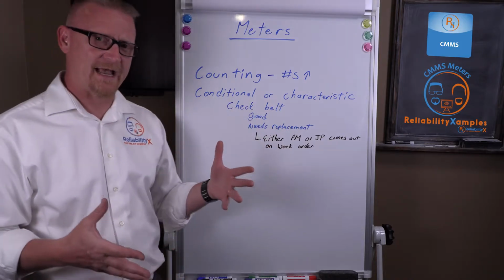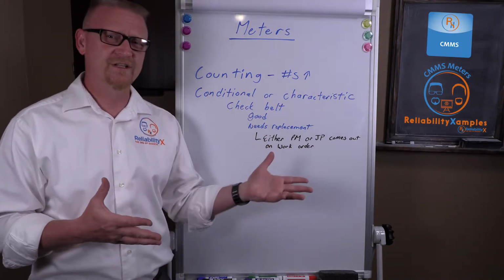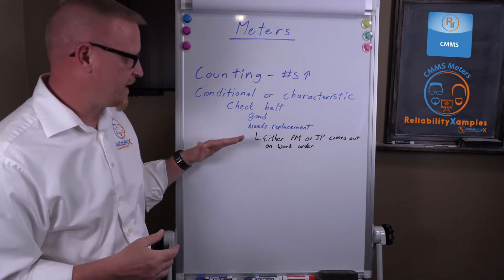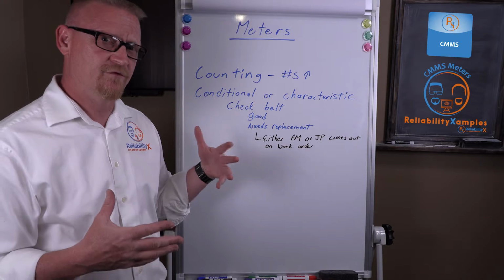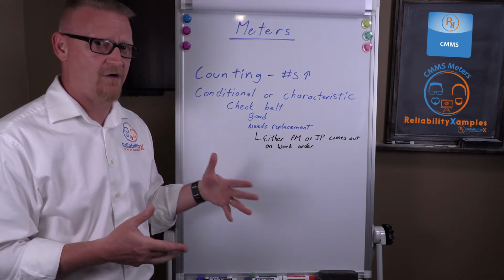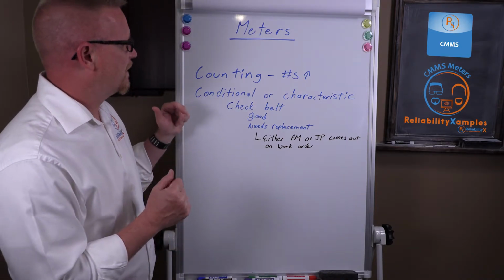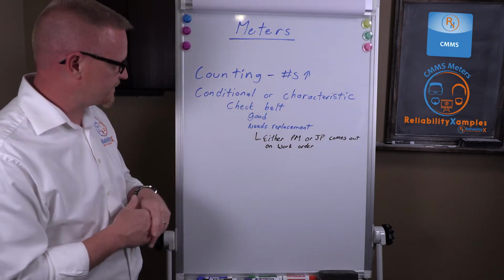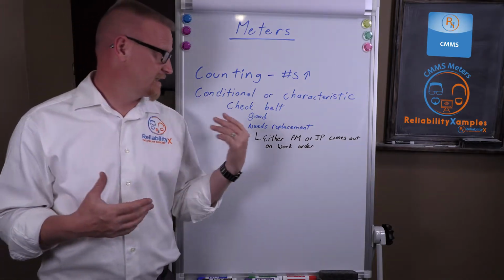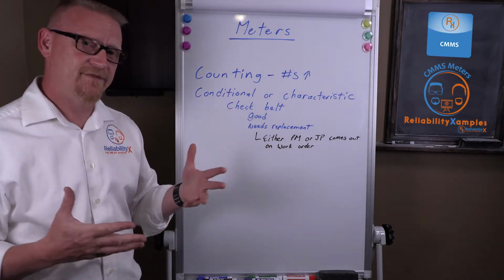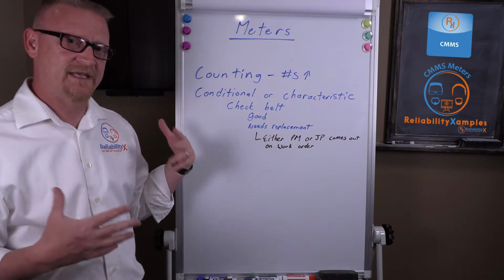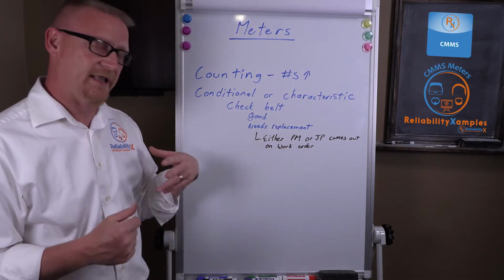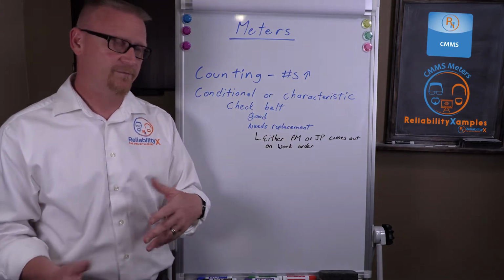And so the response, however, because it's just a belt, is either it's good or it needs to be replaced. We're not going to say the belt is glazed or the belt is fraying. You could, if you really wanted to know the analytics of how often belts glaze versus fray, but for general purposes, we just want to know if it's good or we want to replace it. If the technician selects replace it, then the same thing applies. Replace it ends up being the alarm limit for that meter, and it triggers either a PM or a job plan to come out that says replace that belt.